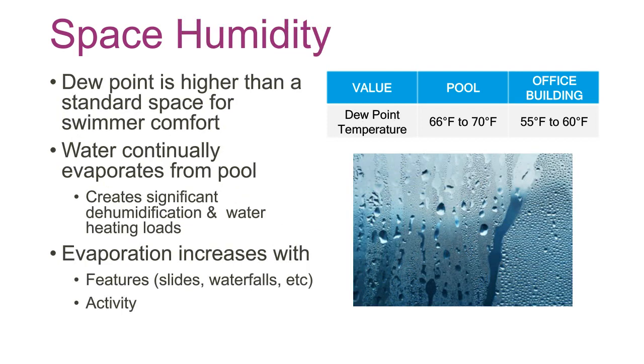affects this application. Another is the dew point or the humidity. You're really trying to keep, like you said, unclothed people really comfortable, and so a lot of times you're in the 60% RH range with that 82 to 86 degree air. So your dew points are 66 to 70 degrees instead of 55 to 60. Water is continually evaporating from the pool, so you have a pool in the space that's different, and it's constantly putting a latent load out there, and that creates significant dehumidification and water heating loads. And then your evaporation, that increases with features, rec features, and activity in the pool.